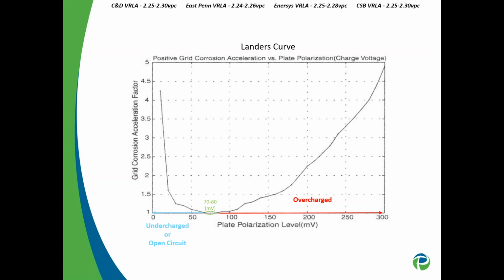The neat part about that is what a battery management system tries to do is hold each battery within those float specification values. When you're setting up your UPS or charging system, you're basing that overall total voltage on the number of cells, so you can get that sweet spot. But because you have one overall charger, there's no way to have every single battery exact without a battery management system on board.